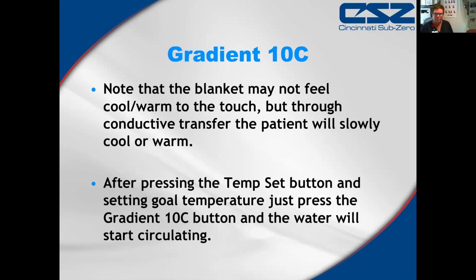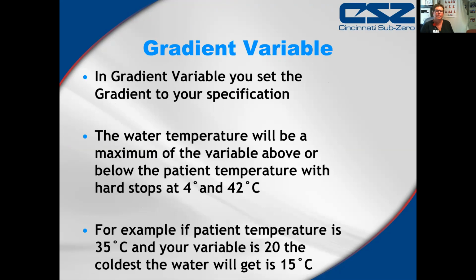Once you have reached target temperature, you are now going to press the temp set button, and you are going to push the gradient 10 Celsius button, and the water will start to circulate. There is also a gradient variable button. And so maybe you are finding that the gradient 10 is not achieving the temperature that you want it, because in the gradient 10, the water will never be more than 10 degrees warmer or cooler than the patient. And so maybe that isn't a big enough gradient.